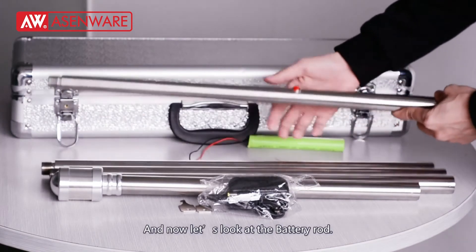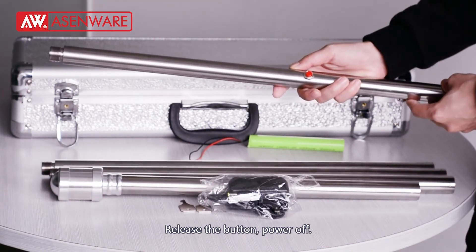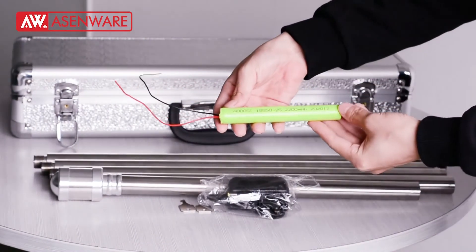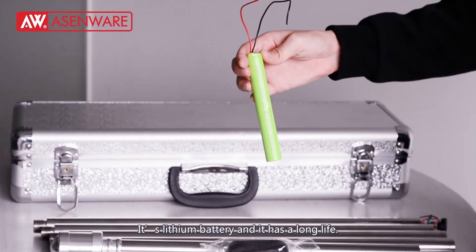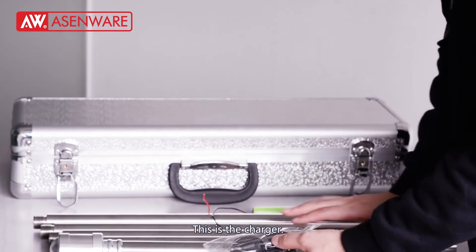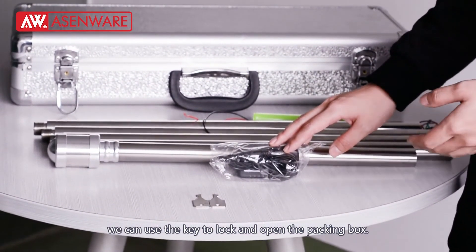Now let's look at the battery rod. We can see there is a button here. Press the button to power on; release the button to power off. And this is where we put the battery inside. It is a lithium battery with a long life. After a full charge, you can test more than 400 flame detectors. And this is the charger — we can use this charger to charge the battery rod. And this is the key; we can use the key to lock and open the packing box, just like we did before.